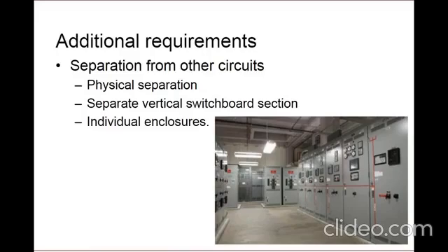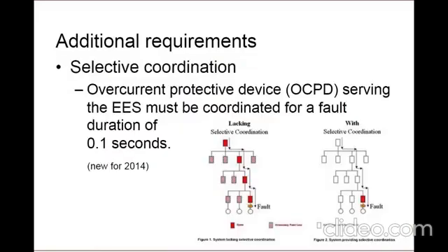And in addition, NFPA 110 requires your EES equipment to be in a separate room from your normal power service equipment. Again, exceptions here apply for smaller services. But it's very important to understand at the beginning of a project when laying out your electrical rooms, because as you can see from the photo here, the equipment can start to get very large once you adhere to all the requirements, and this is just the emergency power room.